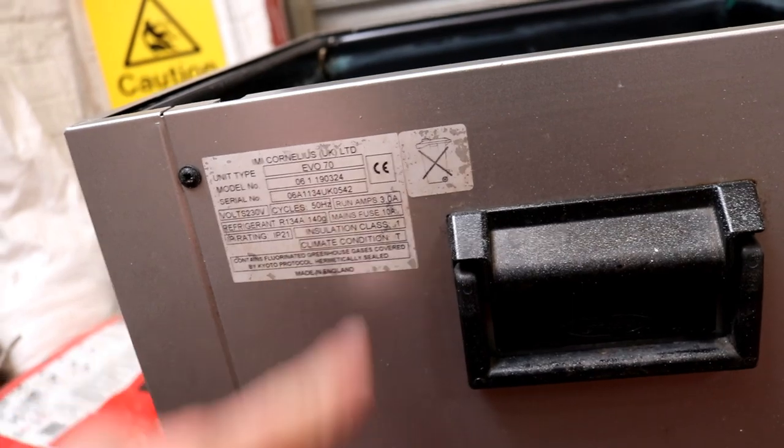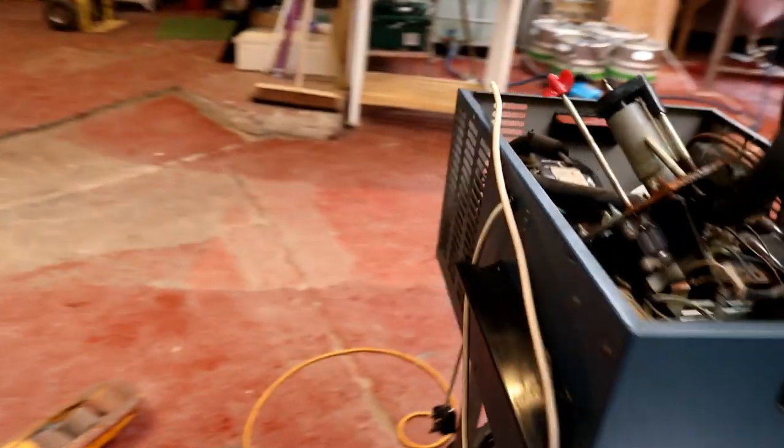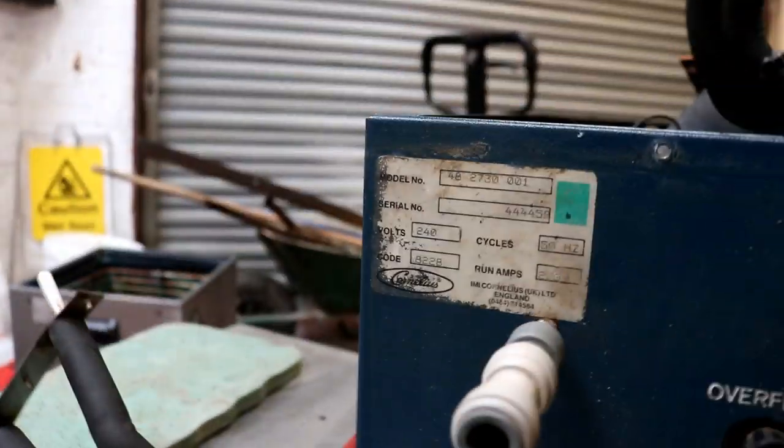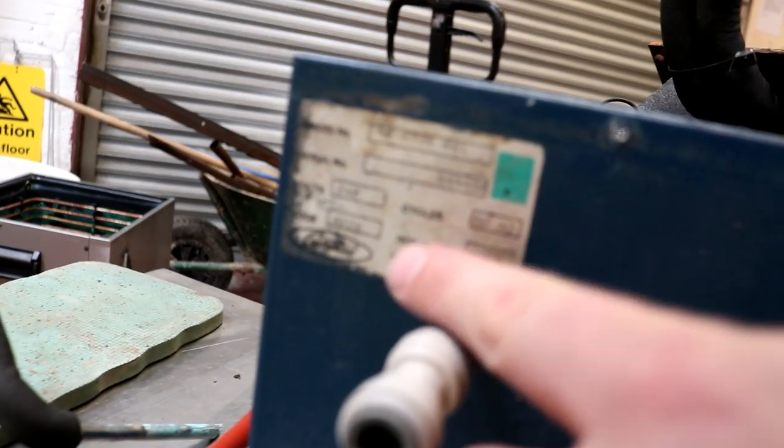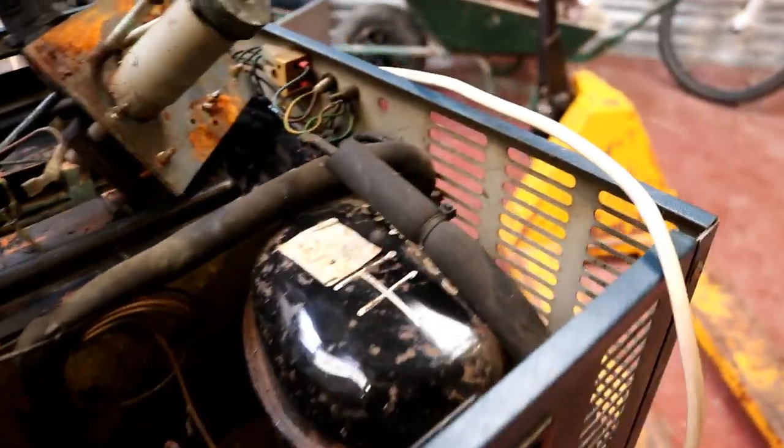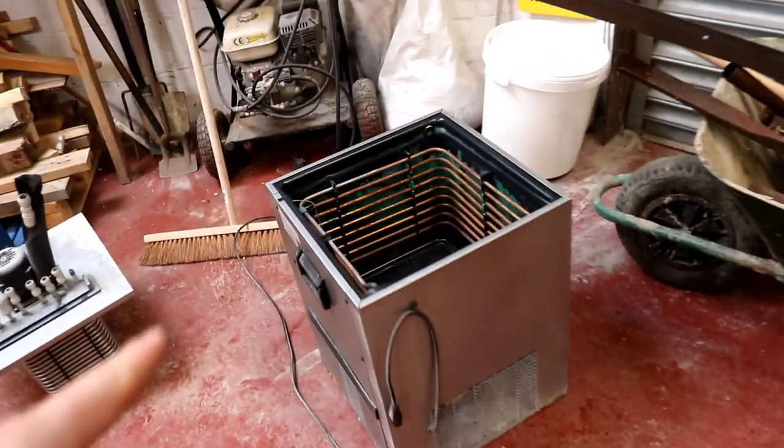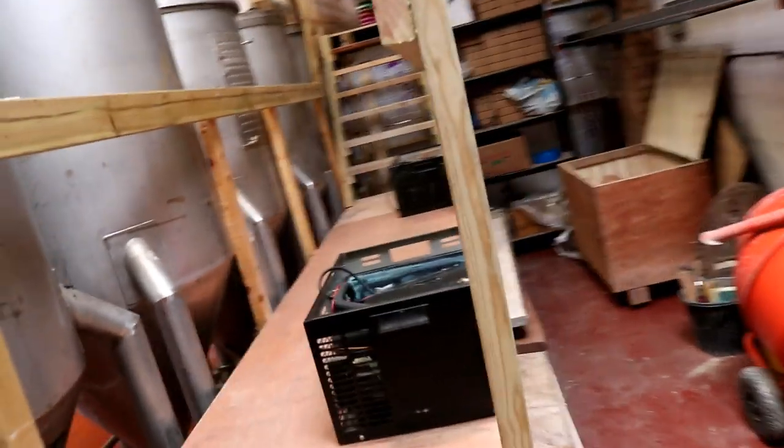There we go, it's an Evo 70. So if that's the case, it's got three amps run, 140 grams of refrigerant in there. Whereas if we have a look at the spec on some of the other units, we've got about two and something amps there. Doesn't quite tell you how much refrigerant's in it, but it's obviously going to be considerably less because it's such a smaller unit.